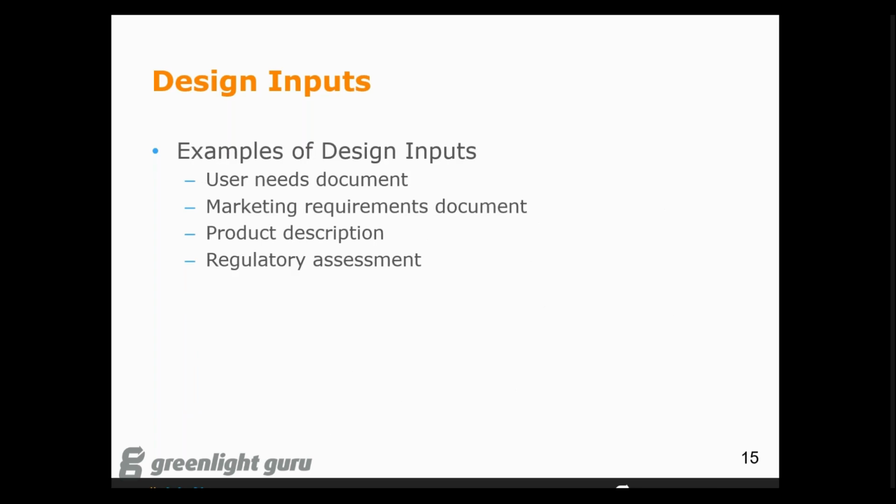So we see various different inputs go into this: user needs documents, market requirements documents, product descriptions, regulatory assessments. All of these things form parts of our design inputs.